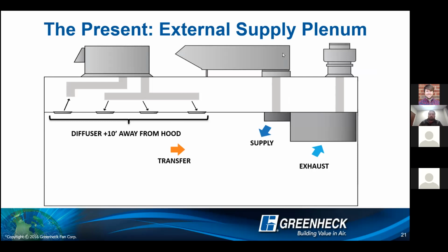So the present. Most kitchens in America today are designed this way, where we're going to have an exhaust fan, best practice being 1 exhaust fan per exhaust collar. Again, fully recognizing that in some instances you have to have multiple exhaust collars to an exhaust fan, but best practice would be to have as close to a 1-to-1 relationship as you can between the exhaust fan and the associated exhaust collars. From there, we're going to have a dedicated makeup air unit that is going to provide supply air through an external supply plenum at the hood.